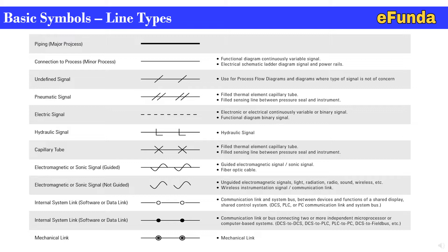The communication link symbol is a dark line with two solid circles connected by dotted lines to two hollow circles. This represents the system bus between devices and functions of a shared display or shared control system such as DCS, PLC, or PC. The internal system link or software/data link uses the same symbol but with two solid circles, representing a communication link or bus connecting two or more independent microprocessor or computer-based systems — DCS to DCS, DCS to PLC, PLC to PC, DCS to fieldbus, etc.